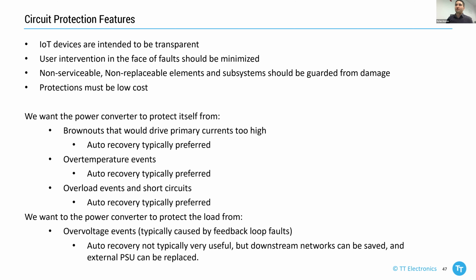The other type of fault we want to look out for, and maybe respond to differently, is overvoltage. Some of the customers I talk to get confused about why overvoltage response on a power supply tends to be latching. The reason is that overvoltage events typically come from a breakage in the feedback loop that's going to drive the supply output to infinity. If we start sending 1,000 volts at your device, we're going to fry all of your electronics. Resetting the power supply is not going to fix the feedback loop, so you've got to cut your losses and turn the whole thing off for good. We'll talk about that in a second.